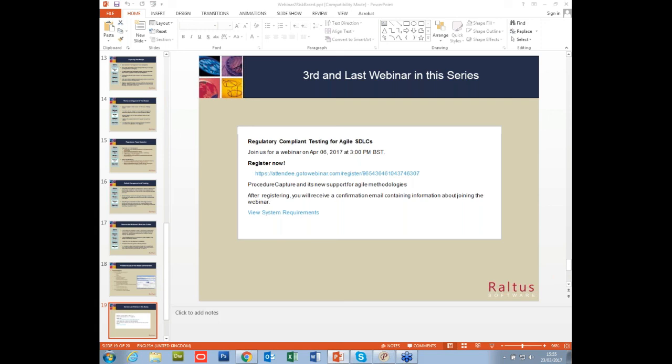But I think in reality, it depends on the system. If you've got a system with a relatively small proportion of high risk requirements, and you scale the testing appropriately, then it is possible to save time. Obviously, the reverse is true. If you've got a highly critical system, you could, in theory, end up spending more time testing than you did. We were in a situation 5-10 years ago where people were doing risk assessments and still doing the same amount of testing that they always did. And then when GAMP5 came out, people thought about it a little bit more intelligently. So there is the opportunity to save time, but there is certainly the opportunity to do more effective testing.